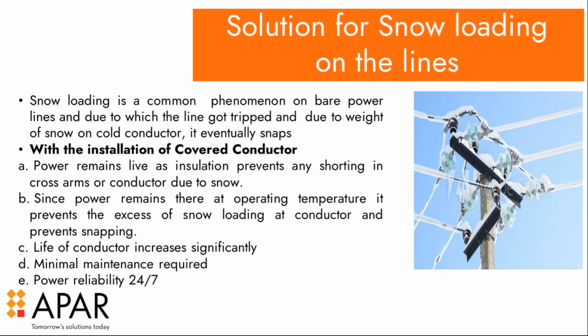Even if there's a lot of ice on the cross arms, since the line doesn't become cold and the operating temperature stays inside, not as much snow gets loaded onto the conductors. The conductor maintains continuity of electricity in the network, giving power reliability of 24/7, and conductor life also increases because there's no snow effect. These are some unique features of covered conductors, which is why they were invented first and then adopted throughout the globe.